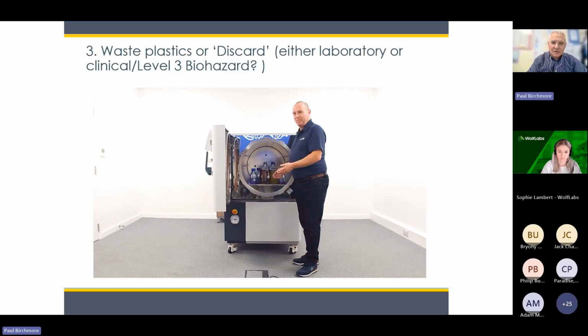So good practice is to see the problems before they arise. Note that if the bag is a particularly compacted load, then make every effort to open the bag or cut the bag to ensure that there's access. And obviously there are some scenarios in that photograph where the correct container for the bag isn't used, and for some peculiar reason, the bag is put inside the autoclave without any containment around it, no discard bin in which to put it. That would only mean that all of the items within the bag will just fall into the base of the autoclave, as that photograph shows, making quite a hideous mess. So you need to use the correct equipment to load the bag as well.